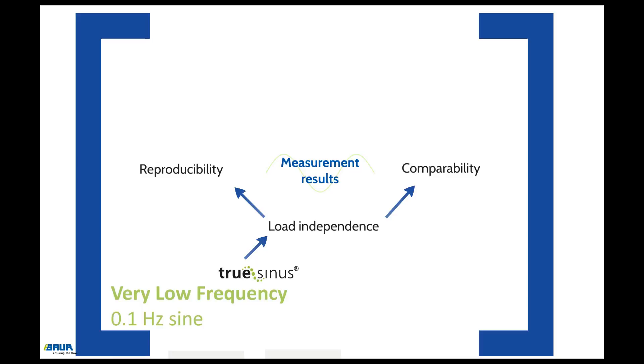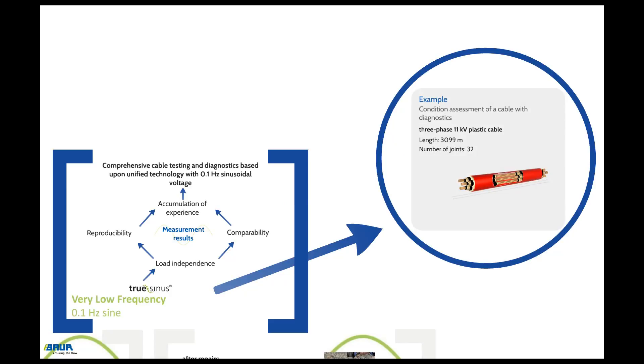Thanks to the comparability of the measurement results, the operator can build up empirical and reference values in the field of dissipation factor measurement and partial discharge testing. This comparability of diagnostic results massively increases the benefits of cable diagnostics. A further advantage is the fact that the sine 0.1 Hz technology can be used for all meaningful measurement methods, such as dissipation factor measurement and partial discharge testing. Comprehensive cable testing and diagnostics is therefore based upon one unified technology with 0.1 Hz sinusoidal voltage. Let us take a look at the benefits and significance of the measurement methods based upon 0.1 Hz sine using an example.